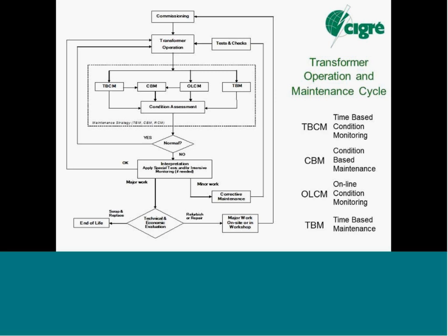To the far right, in that rectangle, we see time-based maintenance, the most basic form of maintenance strategy. And the outcome from these activities is more information on the condition of the transformer. Condition assessment becomes a decision: are things normal or not with the power transformer? If they're all okay, we return the transformer to normal, continued operation.